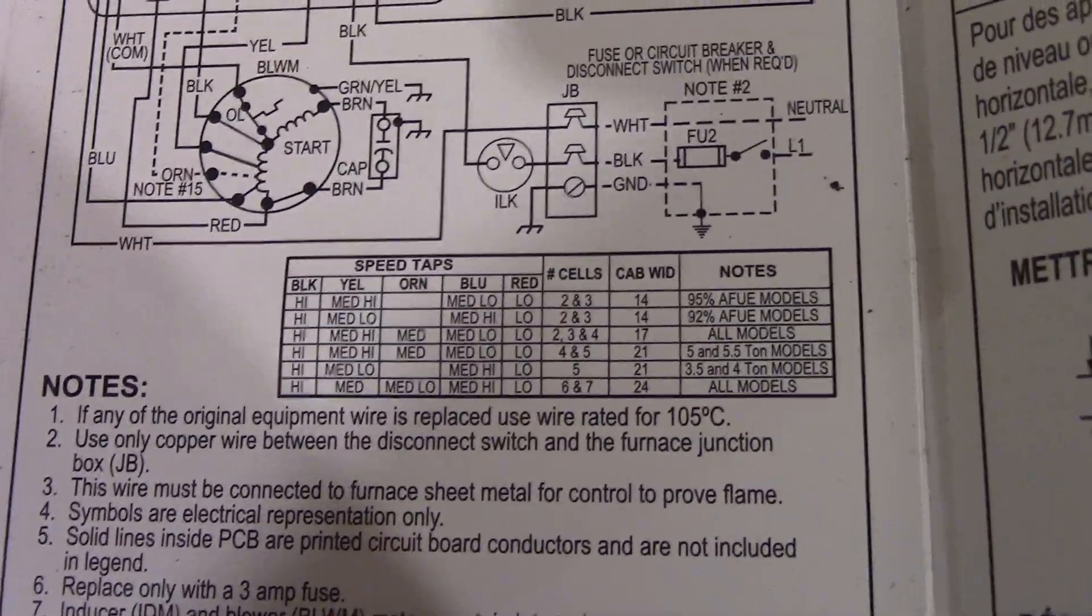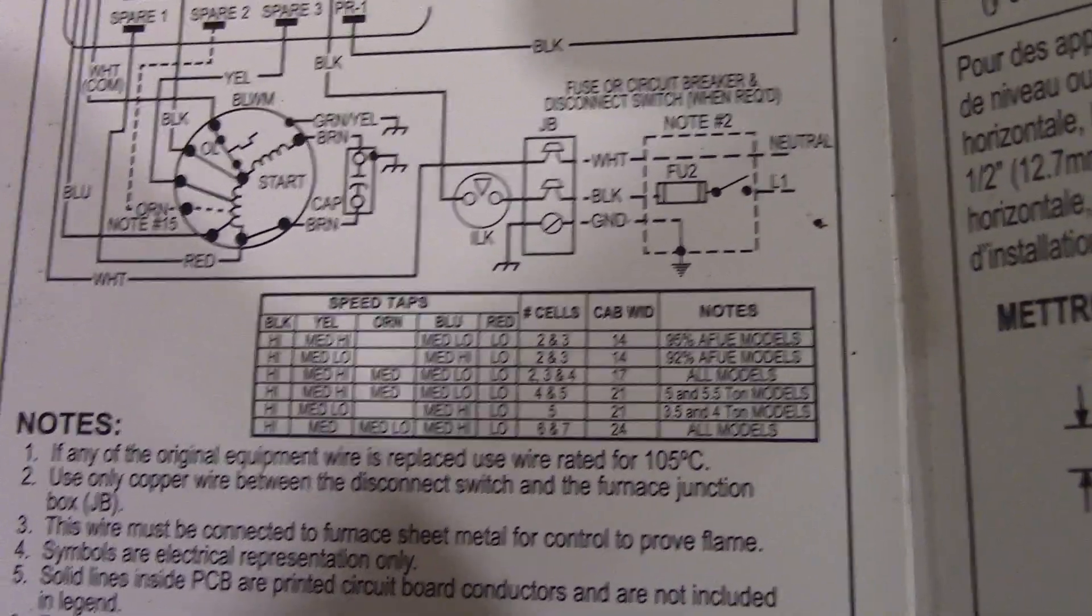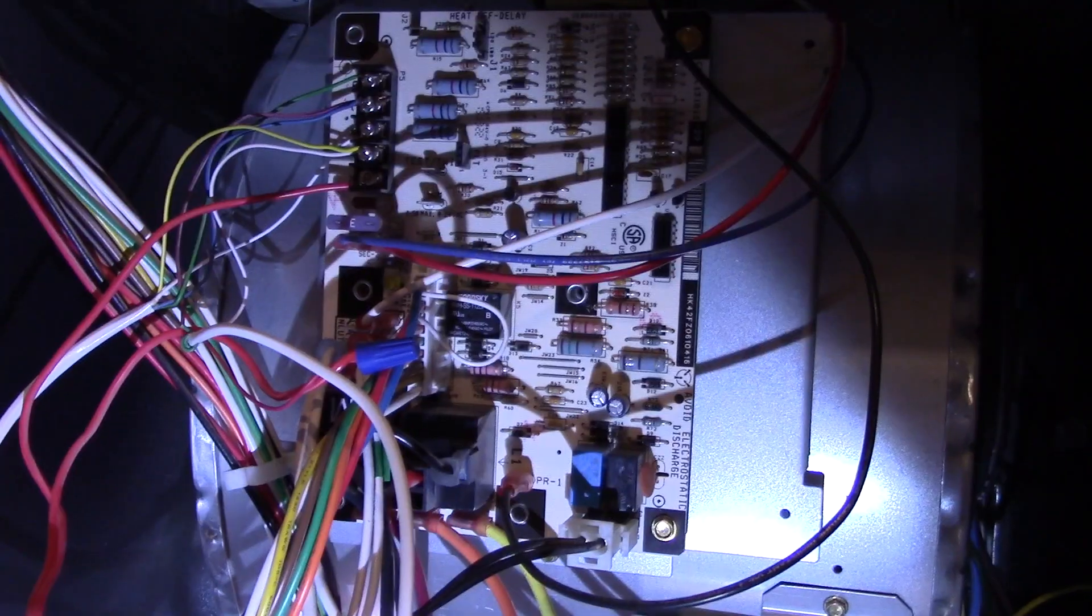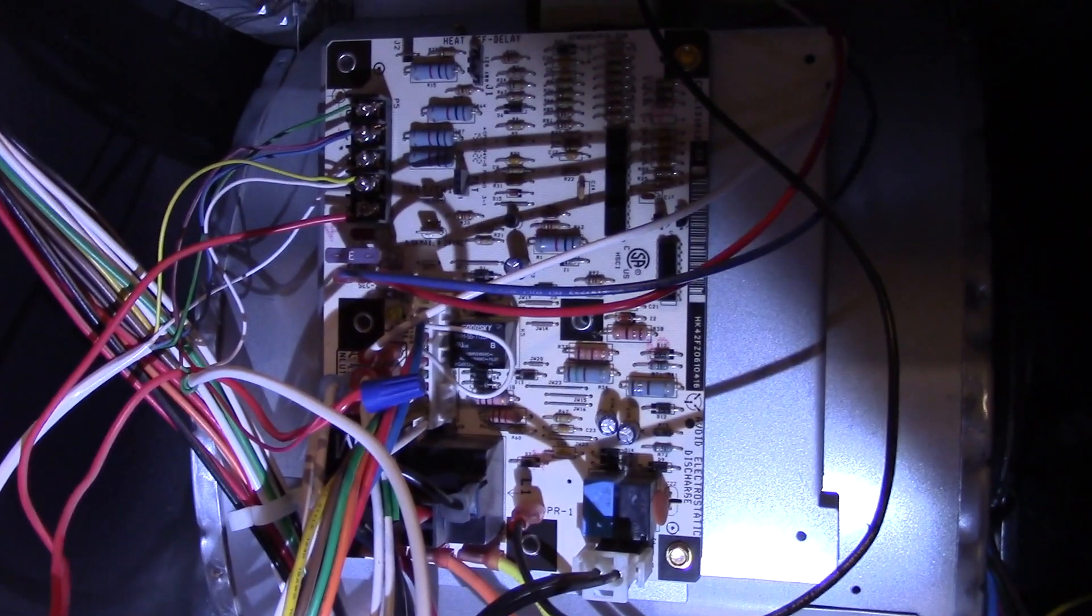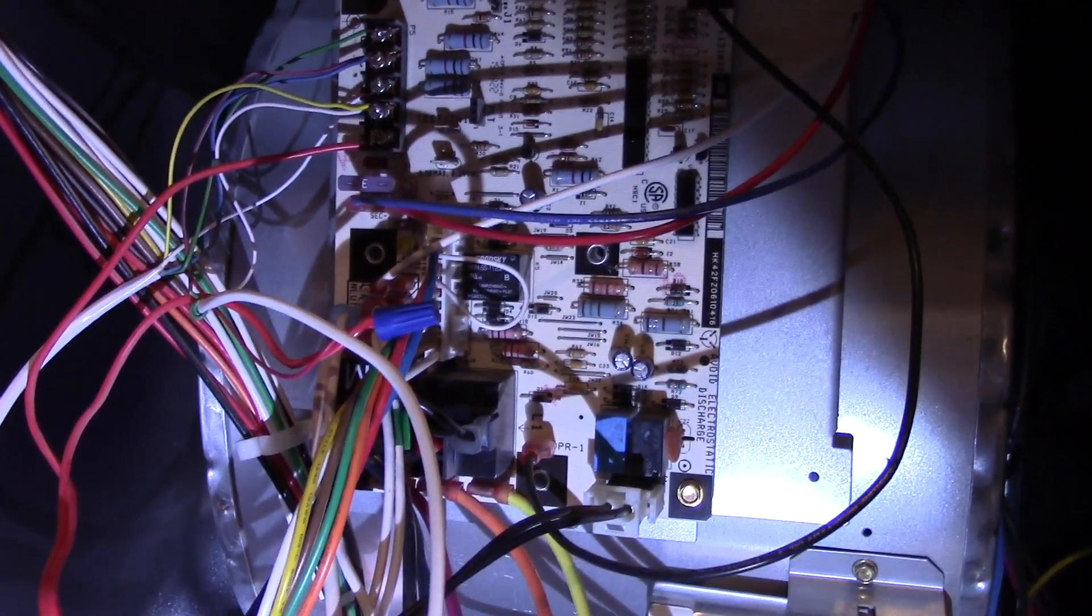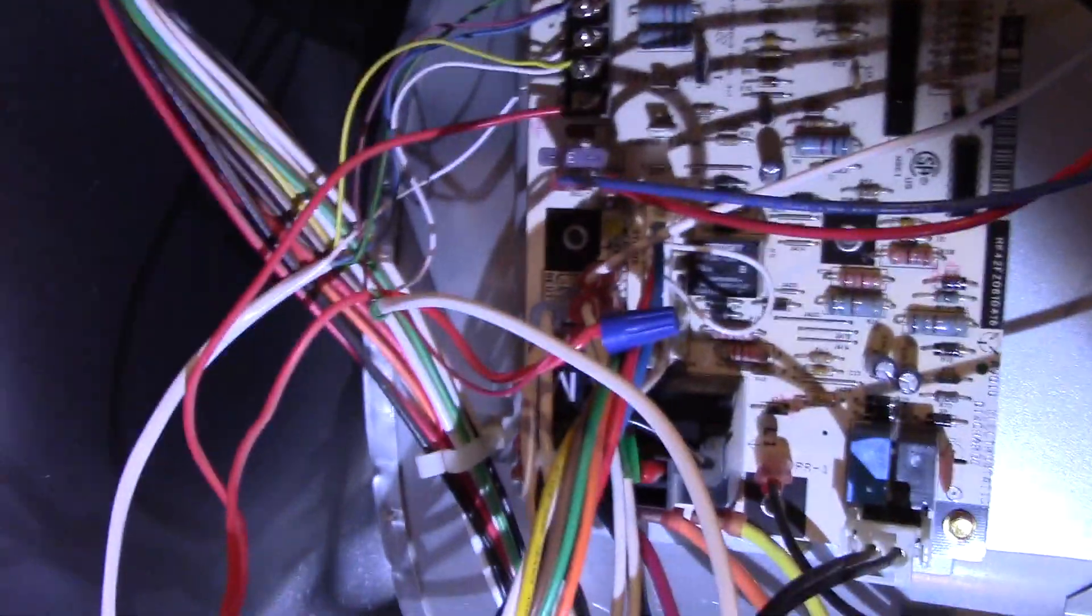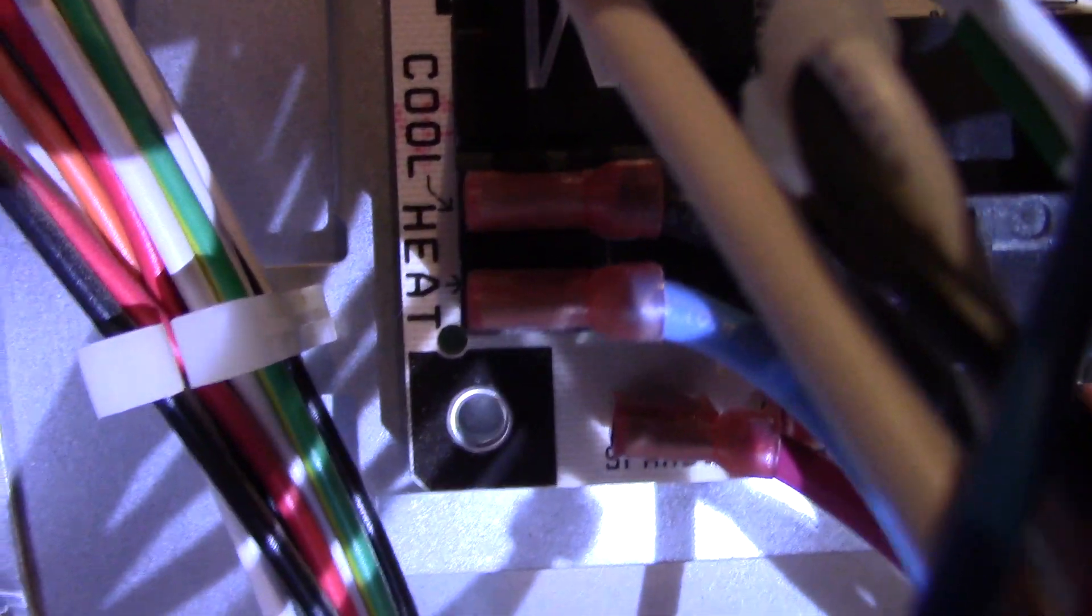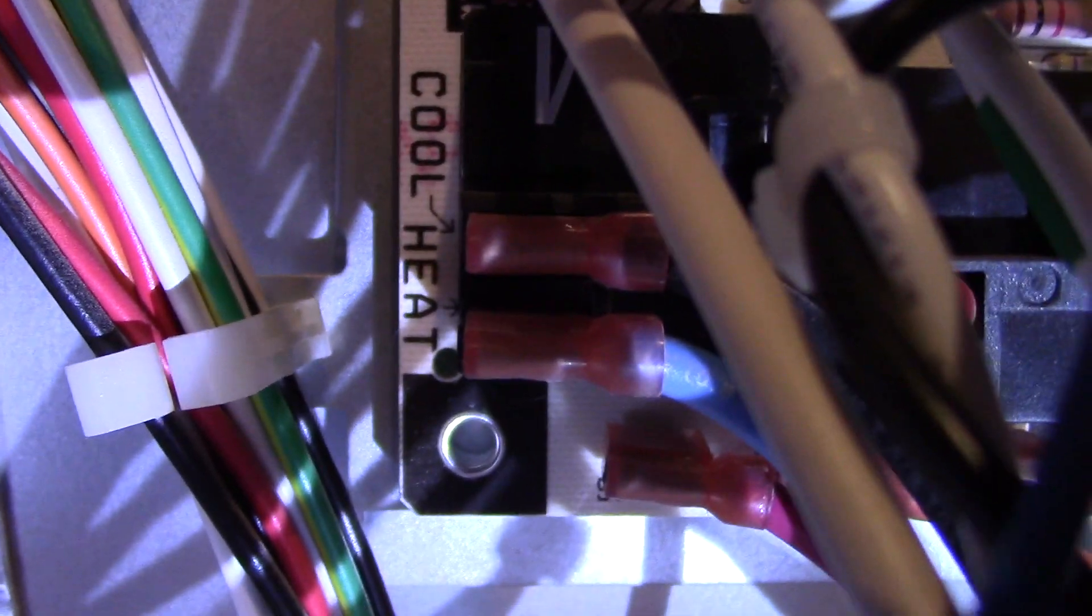Let me show you the circuit board, because that also certainly comes into play as well. Right here is the circuit board, also called IFC or integrated furnace control. What you want to look at is right here. On the left side, you can see a thing that says cool and a thing that says heat. This is pretty much deciding what speed the blower is going to run for which mode, cool being air conditioning, and heat being heat.